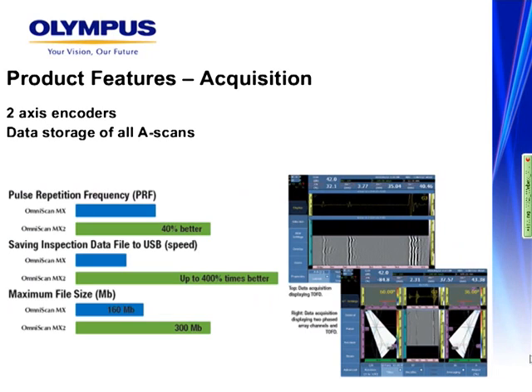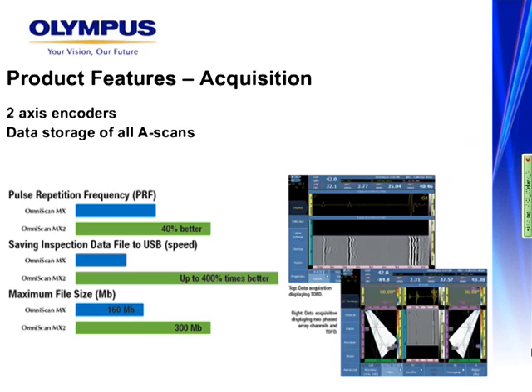A 40% improvement in PRF due to improved electronics, a 400% increase in data file saving and transfer, and an increased file size capacity of 300 megabytes equate to faster inspection times and improved productivity. The PRF is particularly beneficial for the performance and speed of manually pushed encoded scanner applications that are dependent on high PRF for smooth operation and quality data acquisition.